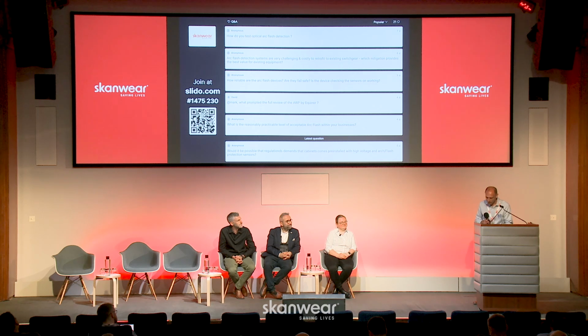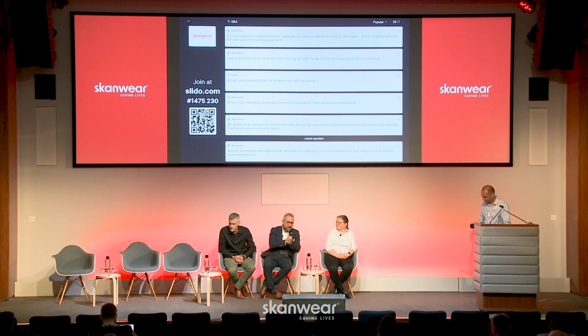Ersin, this is definitely one for you: how do you test optical flash detection? Good question - with a torch we can test the optical sensors. We need to make sure, because these relays now, with new technologies, are talking between each other, that when we're testing we isolate this circuit from the busbar, or the whole busbar will be completely de-energized. If the relays are talking between each other, testing may incidentally trip another relay in a different section, so we need to make sure the network is disabled before testing it with the torch.